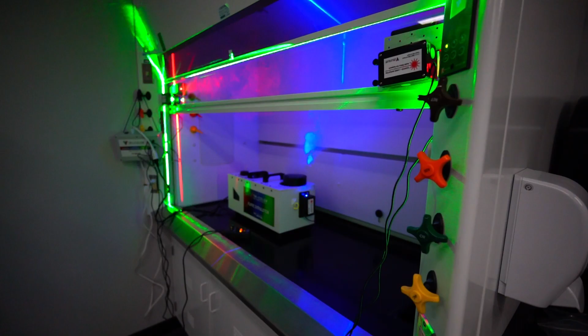Here's an example of a poorly performing hood with its sash fully open. You can tell that smoke and fumes are definitely lazily making their way outside of the chamber into the breathing zone. That's an indication that the hood is performing poorly.